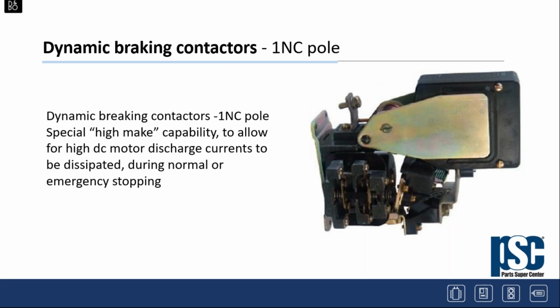We talked about dynamic braking, and I know that term may not be familiar to everybody, but basically a dynamic braking contactor is one normally closed pole, and these are special, I will use the term high make capability, to allow for high DC motor discharge currents to be dissipated, generally into a resistor bank or something similar, during a normal or emergency stop. So dynamic braking contactors have a different application than the normal DC contactor.